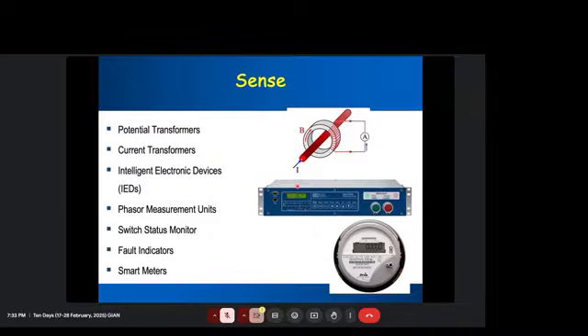It all has a communication link, which handles receiving and processing, and an interface for input, which is analog input. You can configure these systems during manufacturing to decide how many analog inputs, how many analog outputs, how many digital inputs, how many digital outputs you want. This one here is kind of a relay, and it says close and trip, meaning you press this button and it sends a signal command back to the breaker to physically operate it. Of course, if the control command to physical operation doesn't exist at the switch level, it can't do anything — it can only send the signal. But in the circuit breaker, you have to have all the assembly with switching and everything needed to move the breaker to open or close.